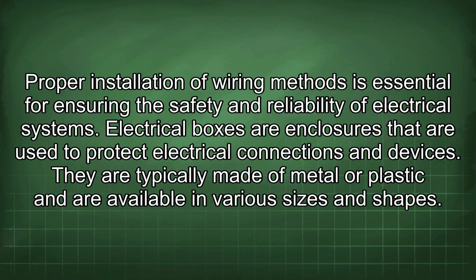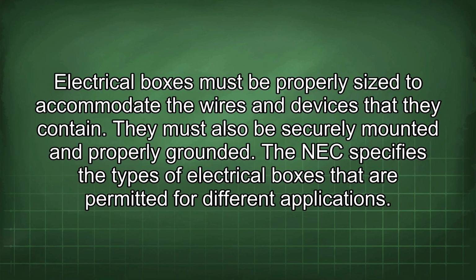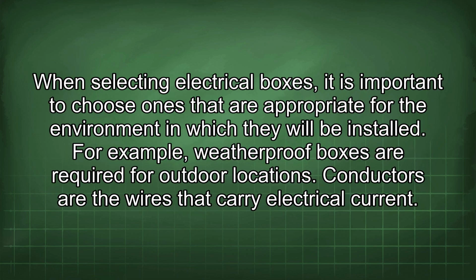Electrical boxes are enclosures that are used to protect electrical connections and devices. They are typically made of metal or plastic and are available in various sizes and shapes. Electrical boxes must be properly sized to accommodate the wires and devices that they contain. They must also be securely mounted and properly grounded. The NEC specifies the types of electrical boxes that are permitted for different applications. When selecting electrical boxes, it is important to choose ones that are appropriate for the environment in which they will be installed. For example, weatherproof boxes are required for outdoor locations.